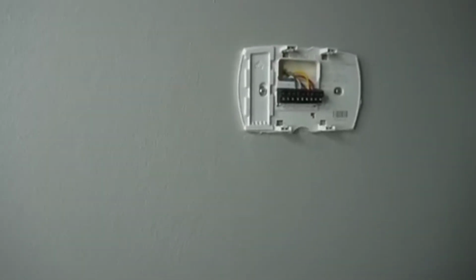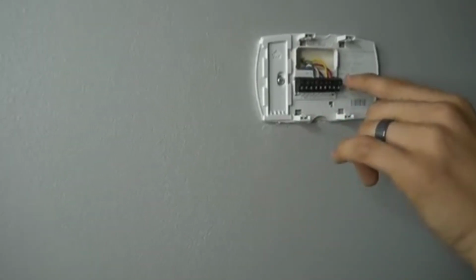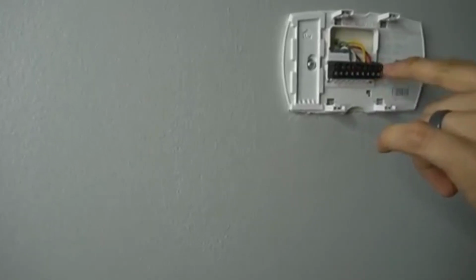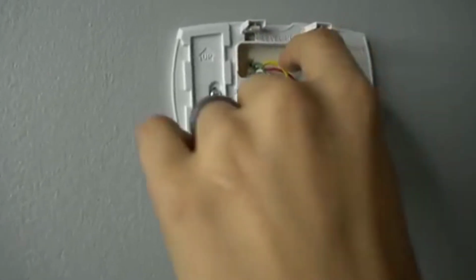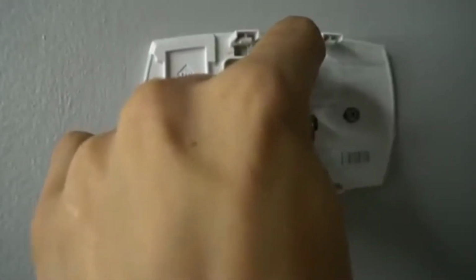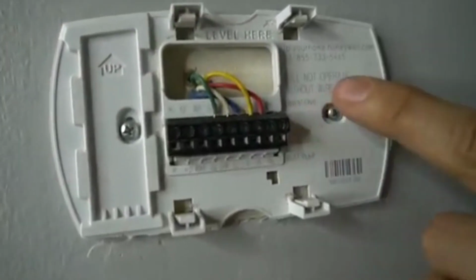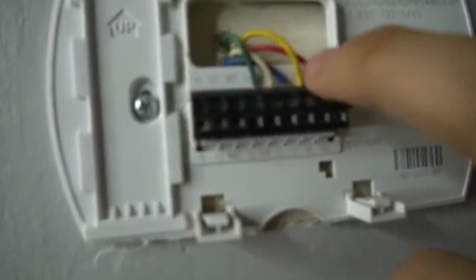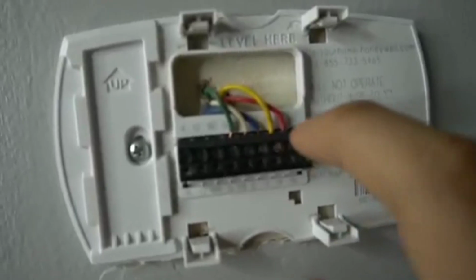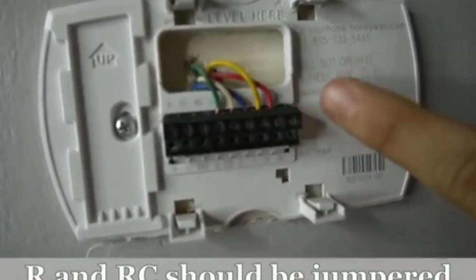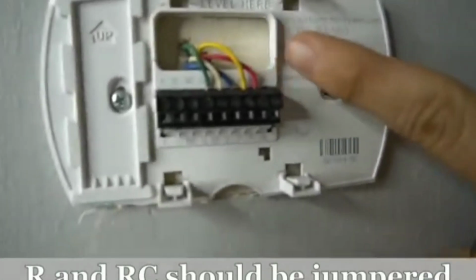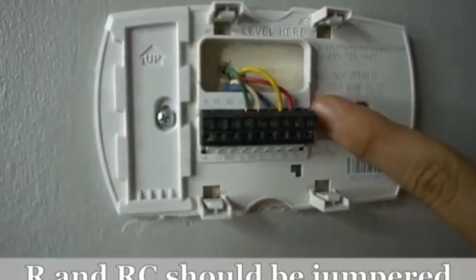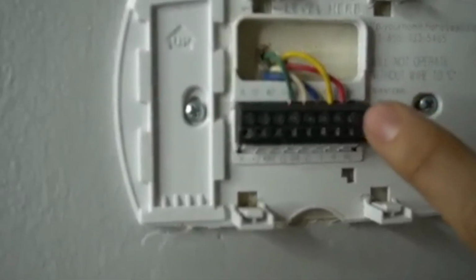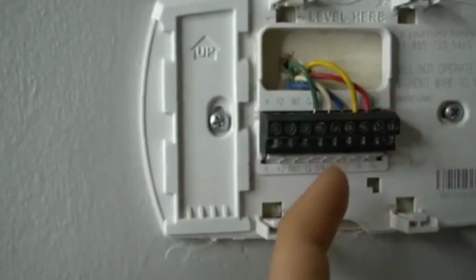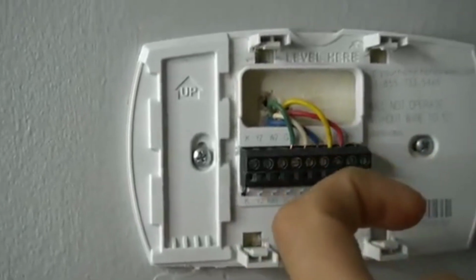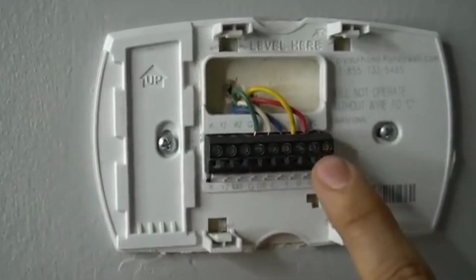Also, if you replaced your thermostat during the winter, make sure that your thermostat has a jumper in between R and RC. If you have R and RC, sometimes you have only the R terminal and not the RC. It's kind of hard to see behind the wire, but if you see right there that little silver jumper that connects my R to RC, that should be in there. RC is power to cooling. So if you don't have a jumper going from R to RC, your air conditioner will not get powered on.